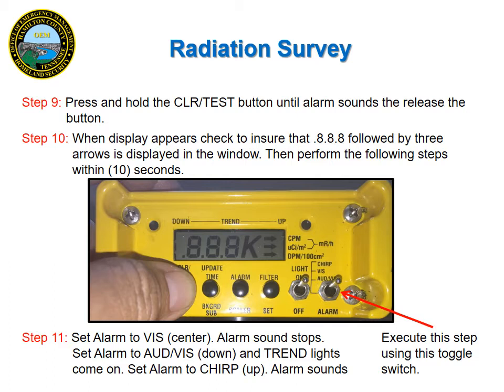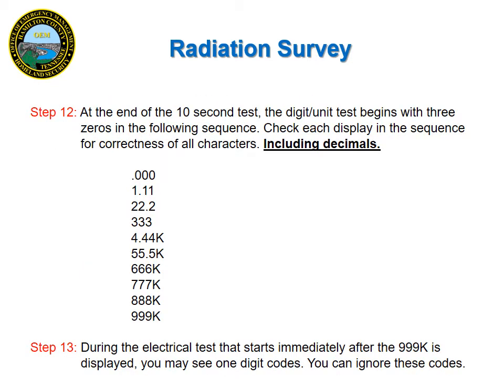When the display shows 3 8s and 3 arrows, you will need to perform the next few steps quickly. You will need to set the alarm to VIS, which is the center position, and the alarm will stop. Set alarm to audio vis, which is the down position, and trend lights will come on. Next, set alarm to chirp, which is the up position, and the alarm will go off again. When you have completed those steps, the digit/unit test will begin with 3 zeros.